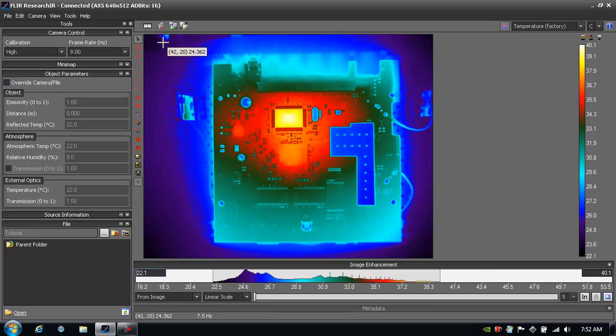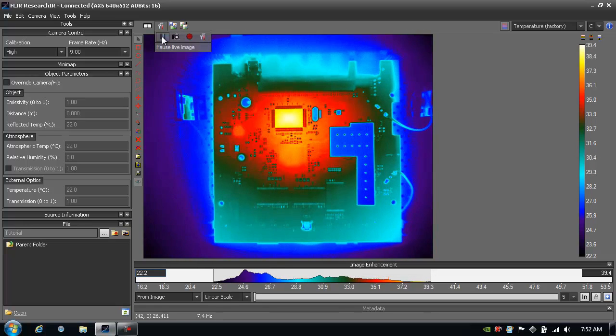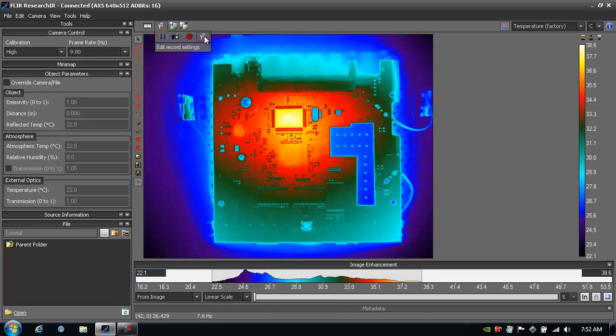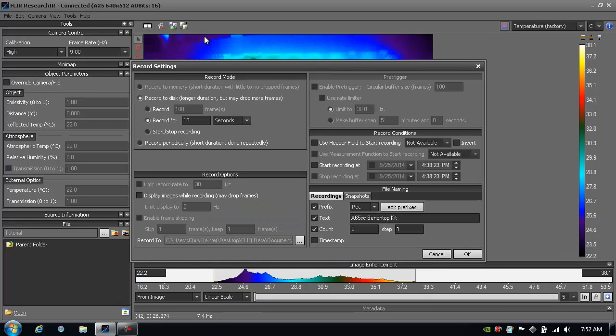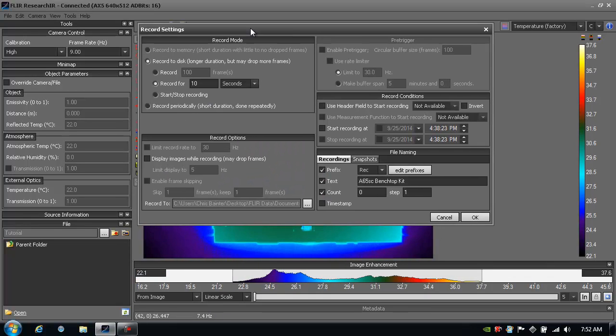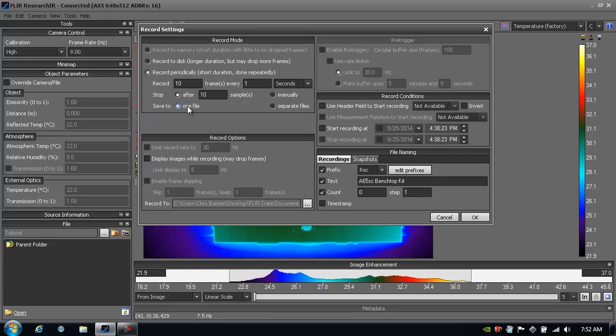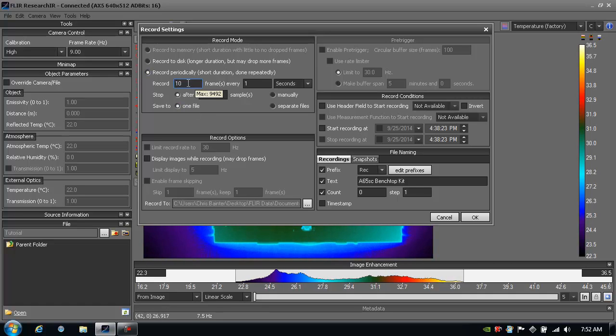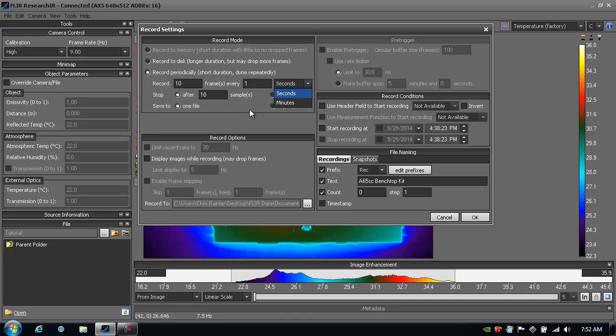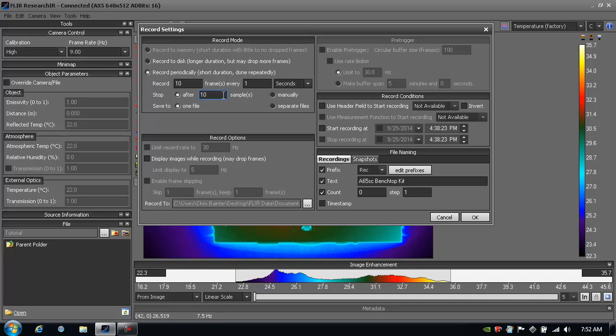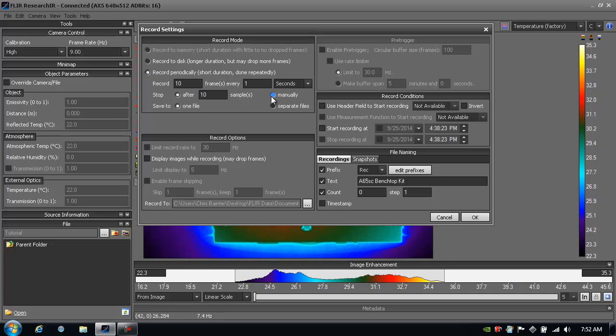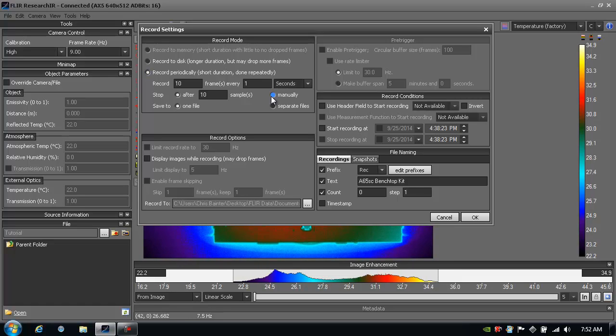To do this, I just go up here to the top, and there's an icon I hover over. And I have a few different options, and the one here on the far right is edit record settings. So I'll click on that, and I have two different record modes available to me with Research IR standard. I can record to disk or disk periodically. Let's take a look at record to disk periodically. Think of this more like a data logger. I specify a certain number of frames to record for a certain duration. Maybe it's a certain number of seconds or minutes. Then I can choose whether I want to stop after a certain number of frames are required or just when I push the stop button. I can also go in and say how I want to save the data. Do I want to save each of the images to its own unique image file? Or do I want to save them all into one movie file that's simple to grab on its own?